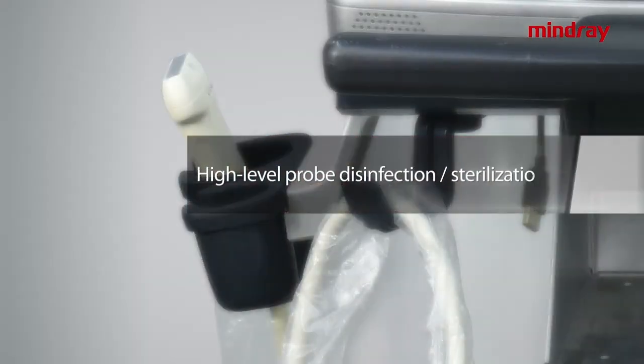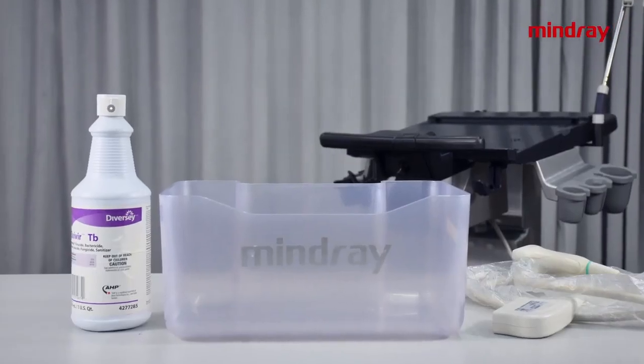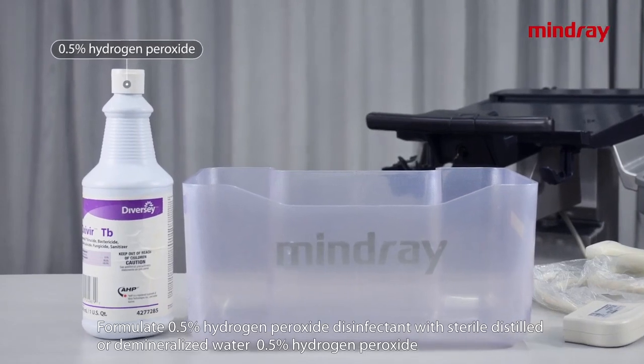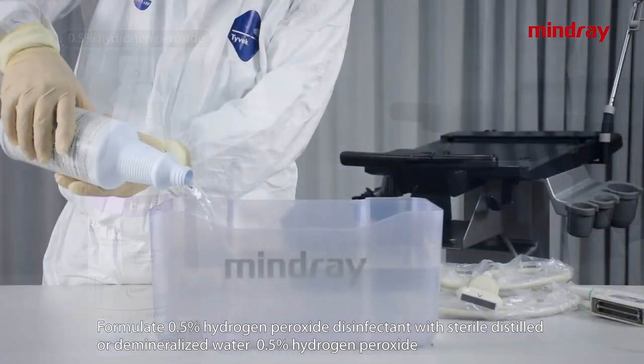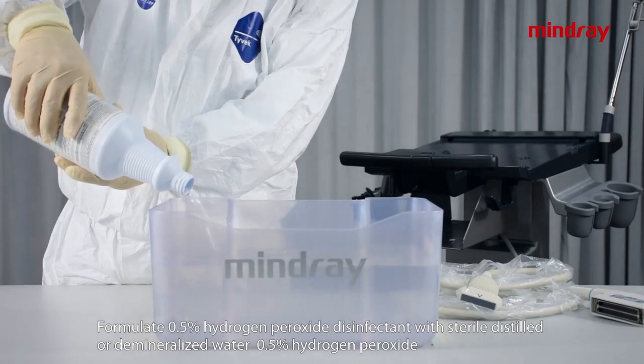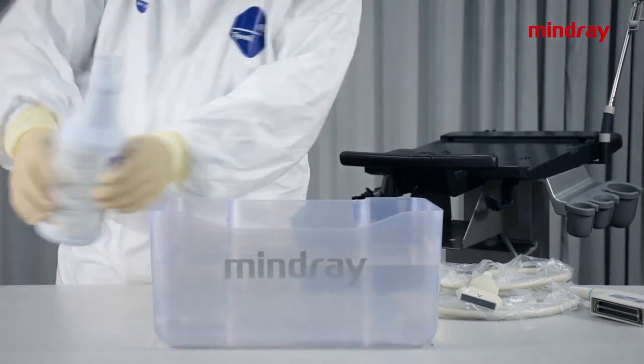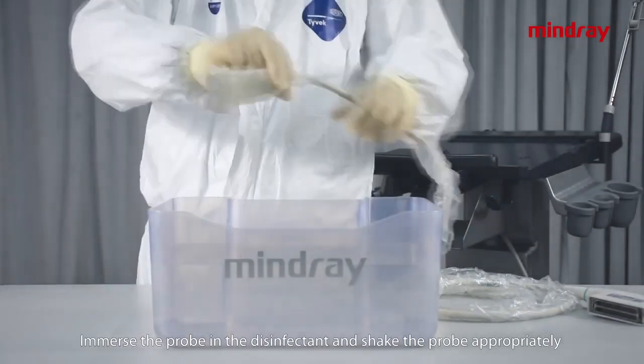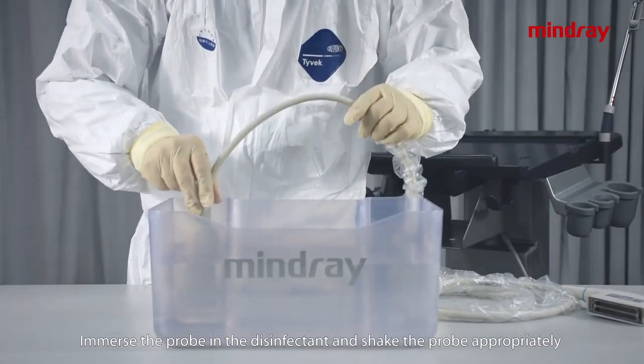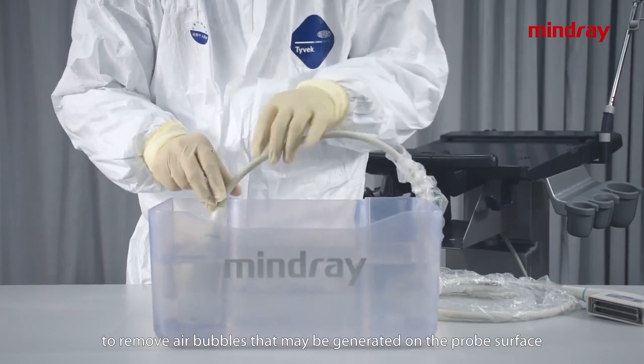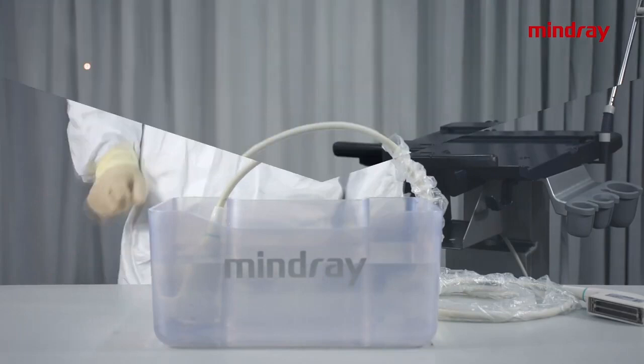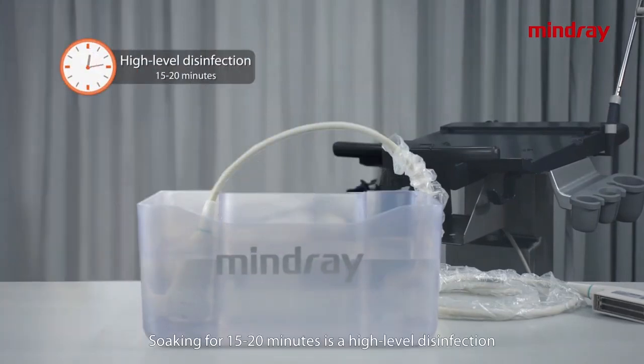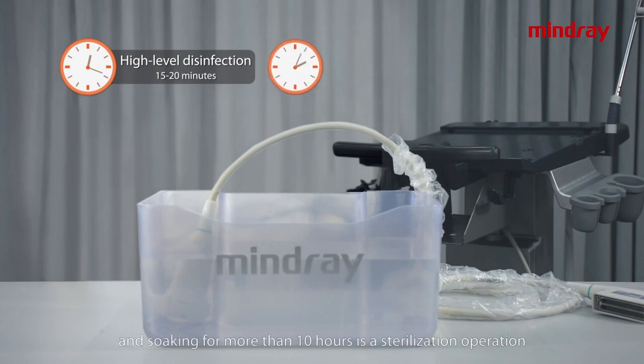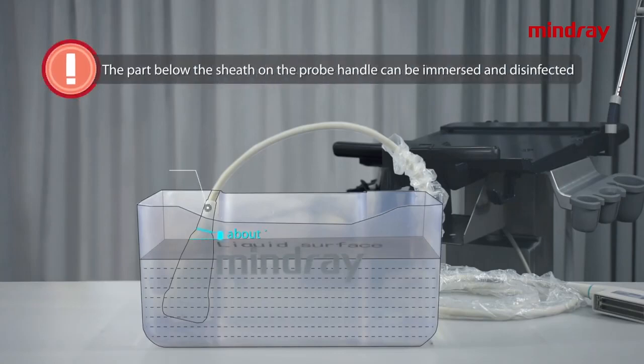High-level probe disinfection. Sterilization. Formulate 0.5% hydrogen peroxide disinfectant with sterile distilled or demineralized water, 0.5% hydrogen peroxide. Immerse the probe in the disinfectant and shake the probe appropriately to remove the air bubbles that may be generated on the probe surface. Soaking for 15 to 20 minutes is a high-level disinfection, and soaking for more than 10 hours is a sterilization operation. Caution: the part below the sheath on the probe handle can be immersed and disinfected.